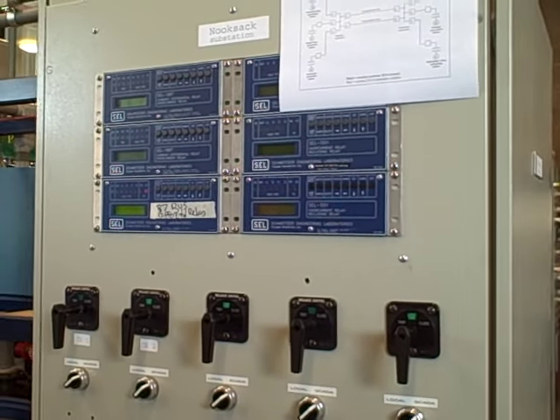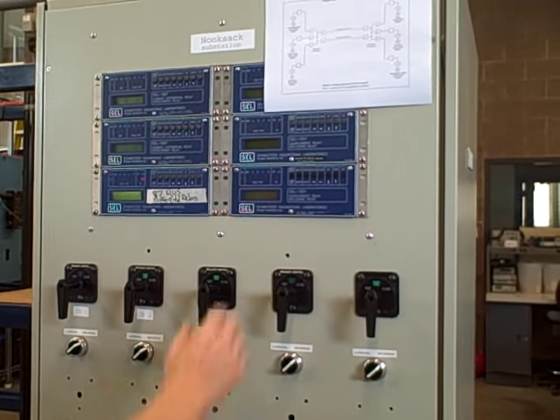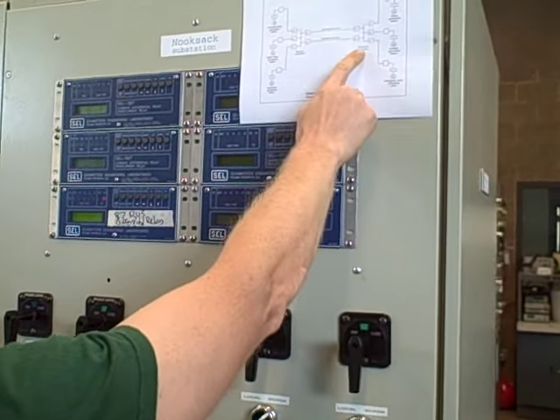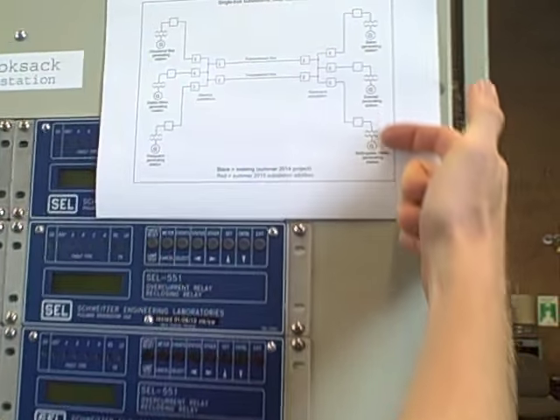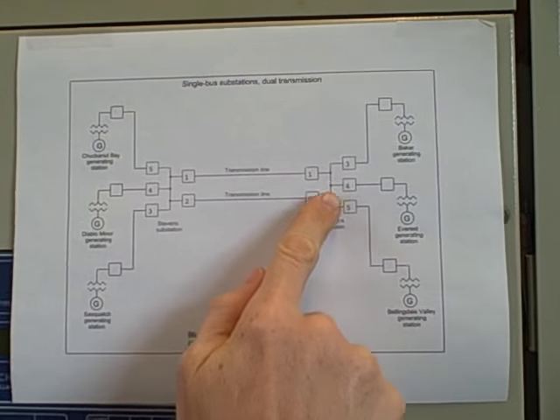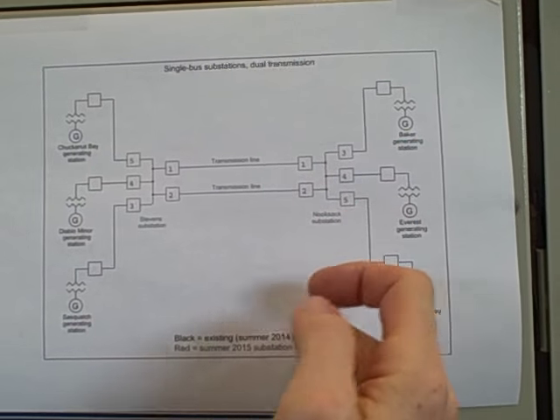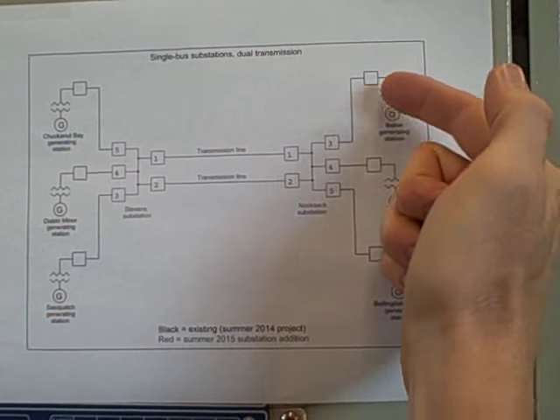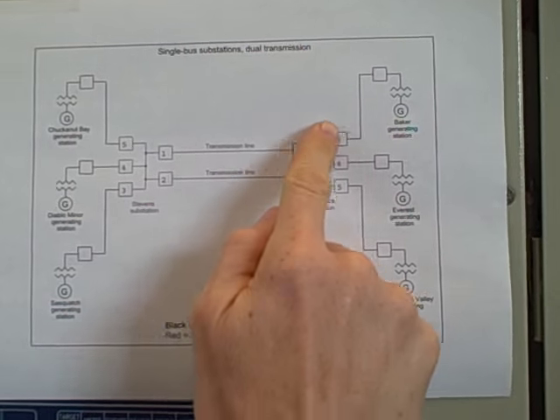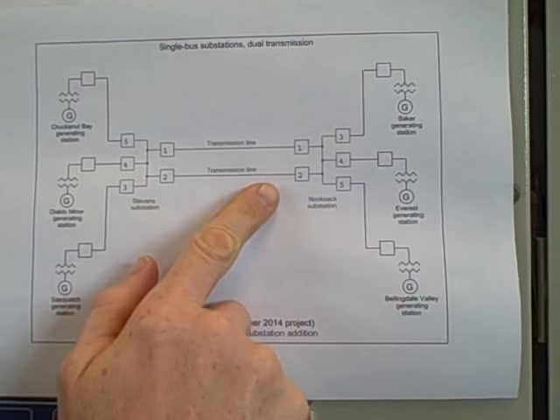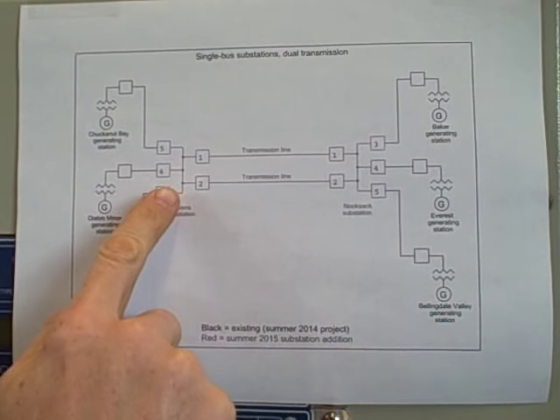We had students pick them as they saw fit. This is our Nooksack substation. As you can tell from the single line diagram, the Nooksack substation ties together three of our generators we built last summer. Ties them together on a single bus through individual breakers. Each generator has its own circuit breaker as well, but these breakers here are in the substation. Then we have a pair of breakers tying to transmission lines to our next substation, which is located over there.